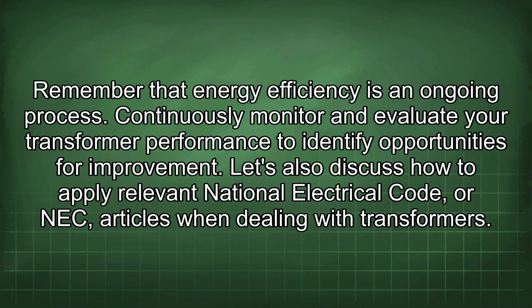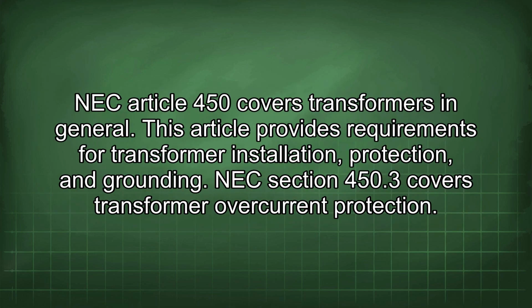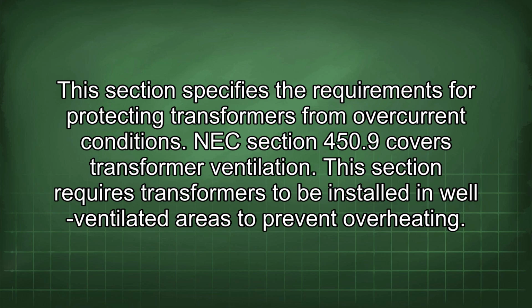Let's also discuss how to apply relevant National Electrical Code, or NEC, articles when dealing with transformers. NEC Article 450 covers transformers in general. This article provides requirements for transformer installation, protection, and grounding. NEC Section 450.3 covers transformer overcurrent protection. This section specifies the requirements for protecting transformers from overcurrent conditions.